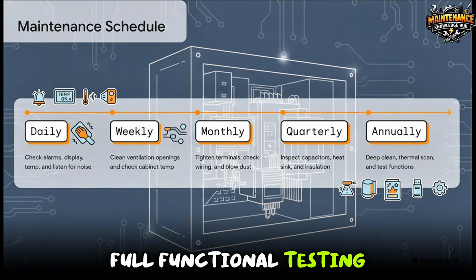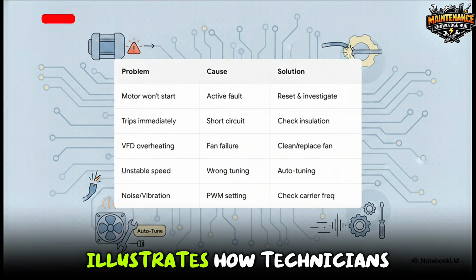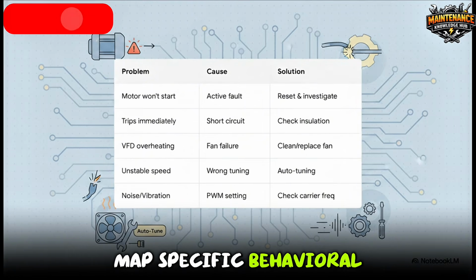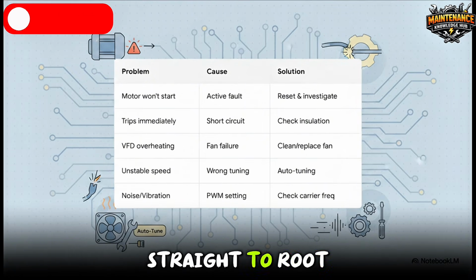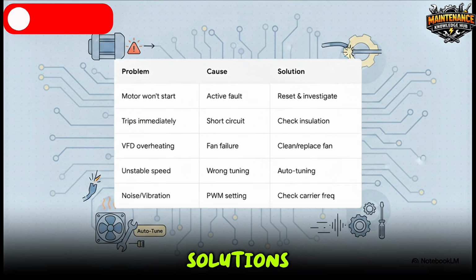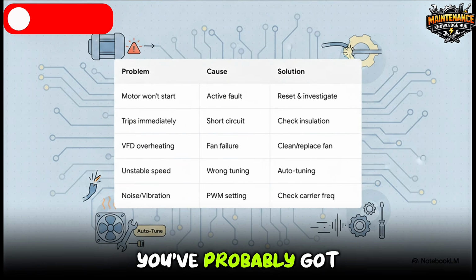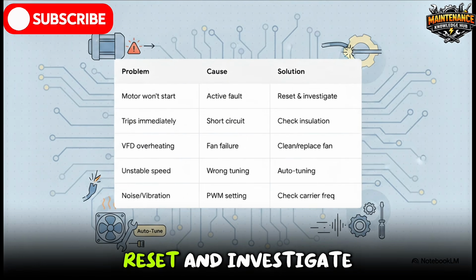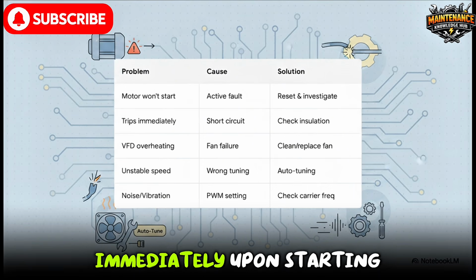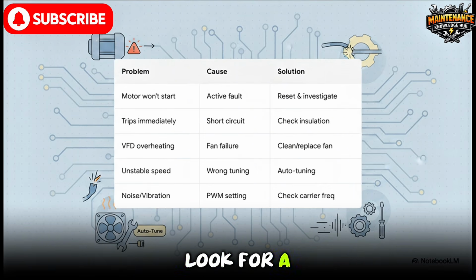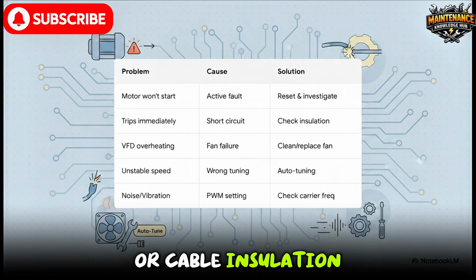and full functional testing. And this brilliantly illustrates how technicians map specific behavioral problems in the field straight to root causes and actionable solutions. Motor won't start? You've probably got an active fault you need to reset and investigate. Drive trips immediately upon starting? You want to look for a short circuit in the motor or cable insulation.